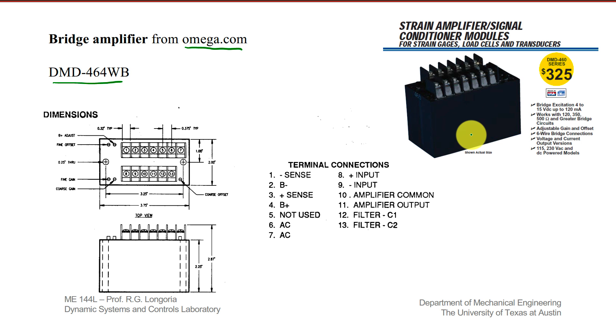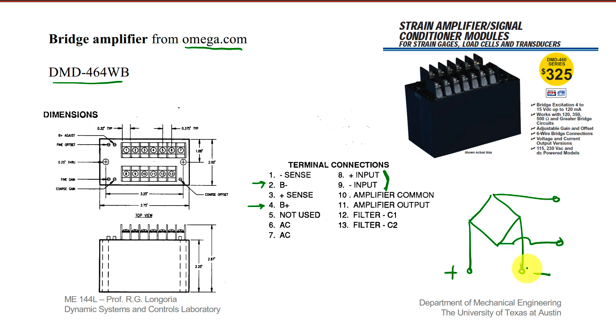The nice thing about these amplifiers is that they have a lot of different adjustments. The input shown here is from the full bridge — let me sketch that bridge again. Here's the output, here's the input. The B-plus B-minus input here is the excitation, so you connect that on the second and the fourth pins. Then the output — designated as the input to the amplifier — uses pins labeled plus-input and minus-input, which is a bit confusing. Those are the inputs to the amplifier, which will be the output of your bridge.